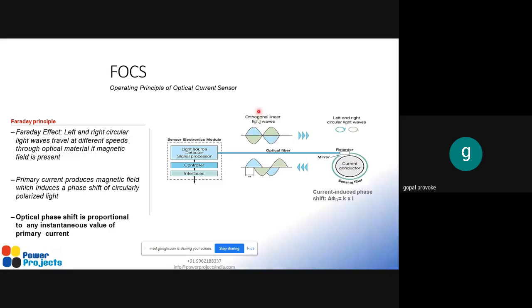This is the original signal which is sent. If you see the arrow mark, this is the signal sent to the current carrying conductor, and this is the signal reflected using the mirror, which is received back at the source. After receiving this reflected light, we see a phase difference between the two lights, and this optical phase shift is proportional to the instantaneous value of the primary current.